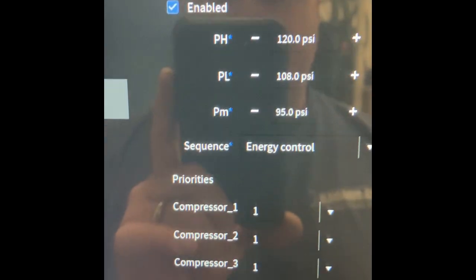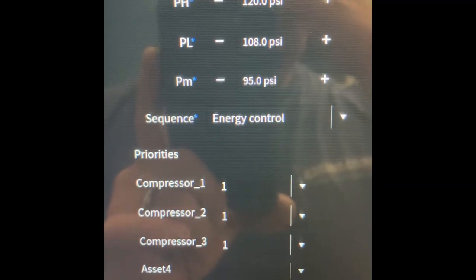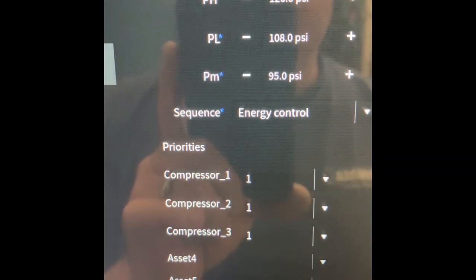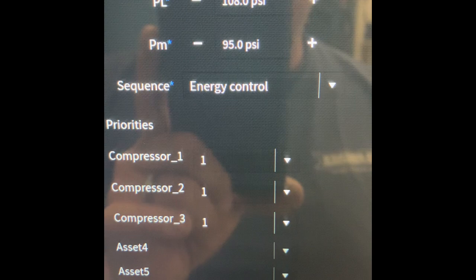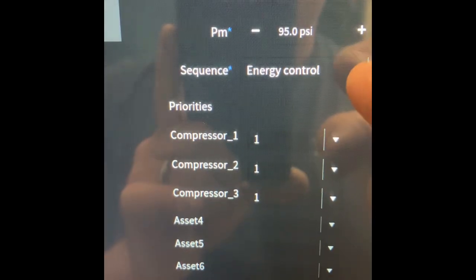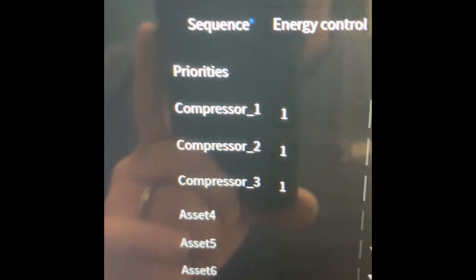And then we need to set our pressure table, table 1. I set it to match exactly what I set in the T1 earlier - so 120, 108, 95 minimum. Sequencing is energy control, and they're all priority 1.